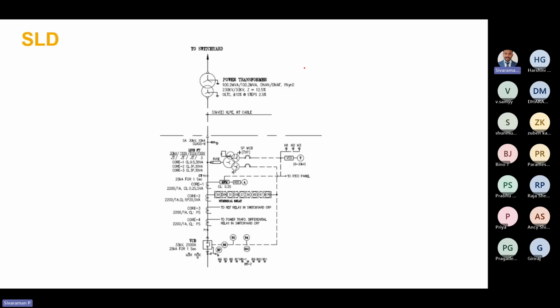So moving further, this is the transformer. This is the power transformer of 100 MVA. So it has a power rating of 100 MVA. It is ONAN, ONAF type. So we can use this transformer as ONAN, oil natural air natural, as well as ONAF, oil natural air forced. It has the vector group of YN, YN. So both sides are star, that is YN, YN, star grounded, star grounded.